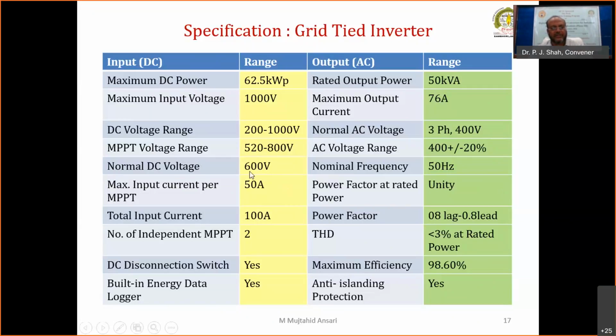The nominal DC voltage is 600 volt. The maximum DC current is 50 ampere. So while connecting the number of PV modules, again we have to calculate the maximum current, and it should not be more than 50 ampere. Now one more point to be considered here. A disconnecting switch should be there, and built-in energy data loggers, which will give the energy generation by that particular inverter in a day, in a week, or in a month or year. In all types of inverters, these facilities are there. Also the maximum efficiency, average power factor, and all these things.